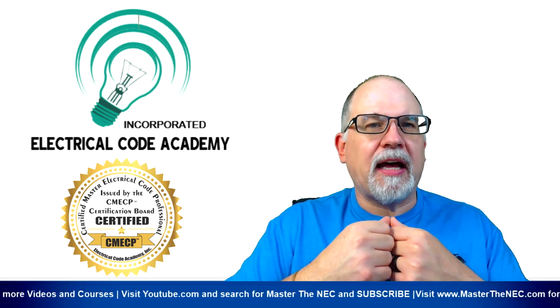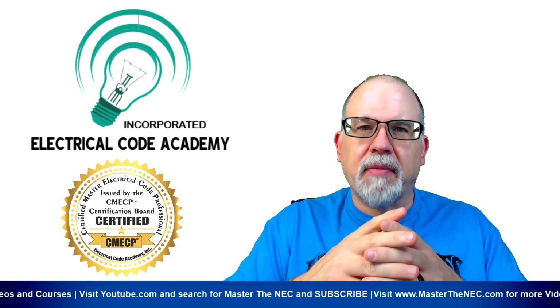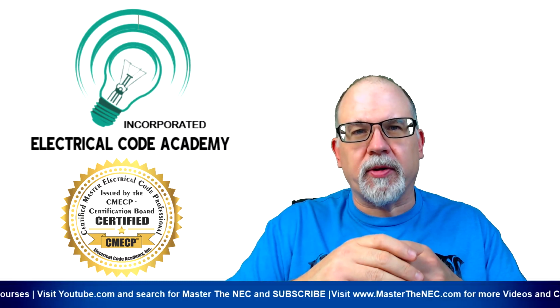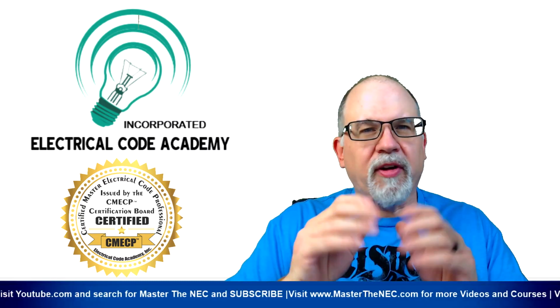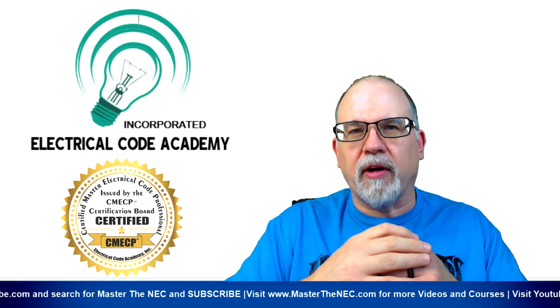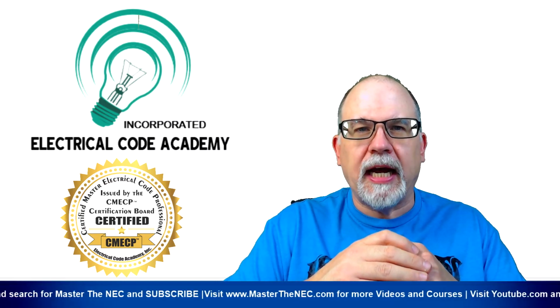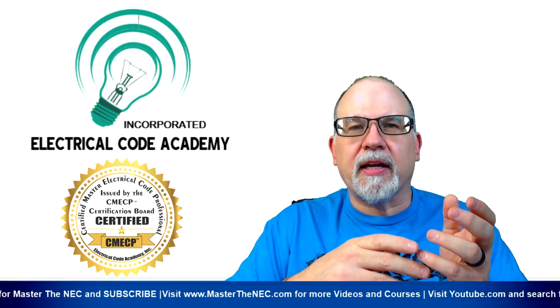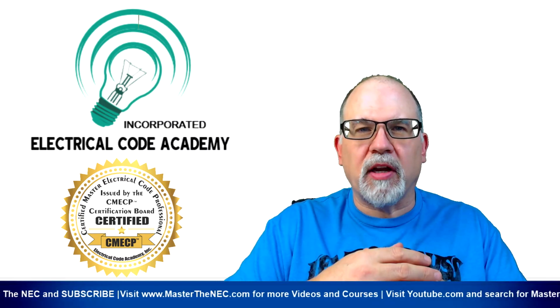Now, we're going to talk about how to size the supply side bonding jumper, the system bonding jumper, and grounding electrode conductors. We're going to be very brief with that because we have a whole other series on grounding electrodes and grounding electrode conductors. We're going to talk about the equipment grounding conductors that are brought to the primary side of that transformer.